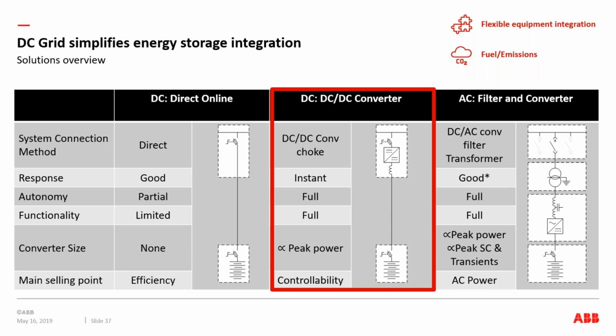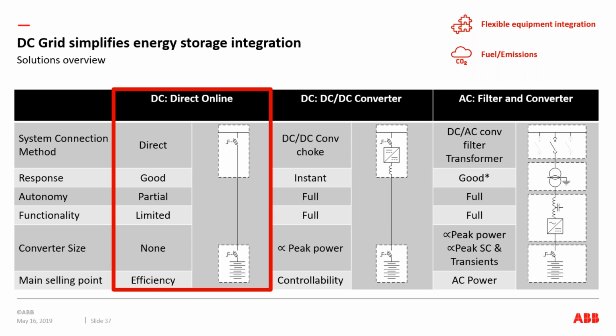So in order to maintain constant voltage on the bus, we would typically use a DC-DC converter as shown in this arrangement. However, if batteries are your sole or majority source of power, it sometimes makes sense to consider doing a direct online battery, accepting that your bus voltage will vary throughout the day as the state of charge changes. You have to design the rest of the system to accommodate that, but it's certainly possible, and it simplifies the design a little, makes it more efficient with one less conversion step, and reduces the amount of equipment on board and the CapEx associated.